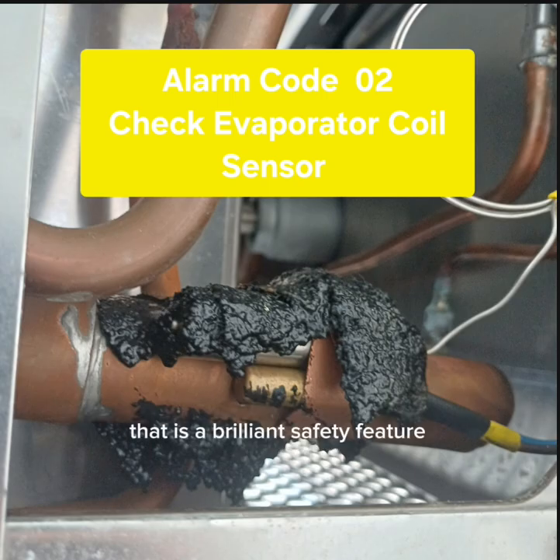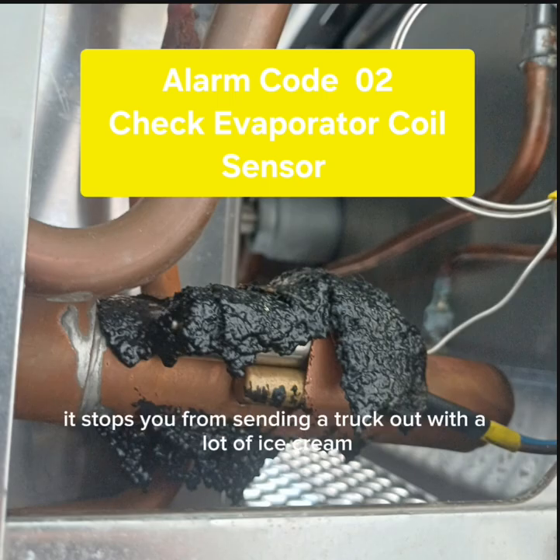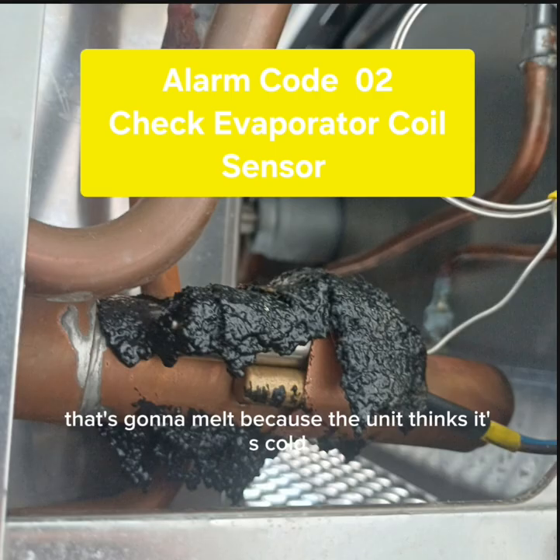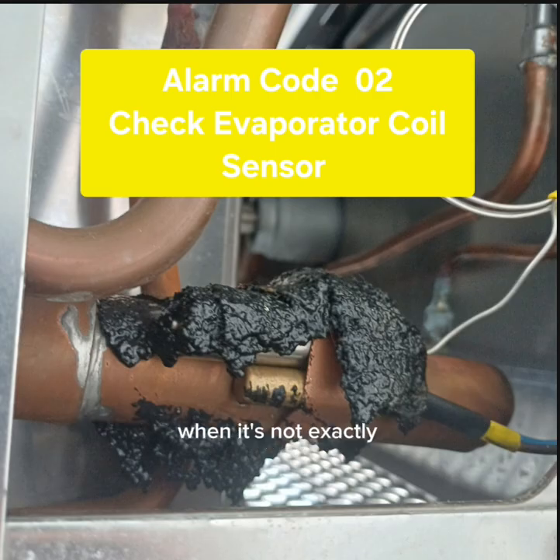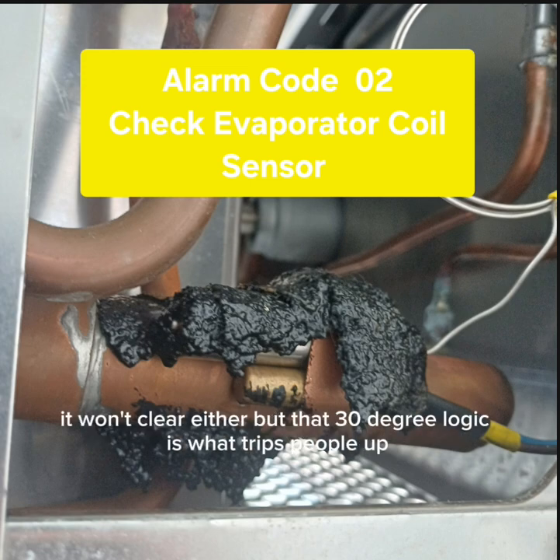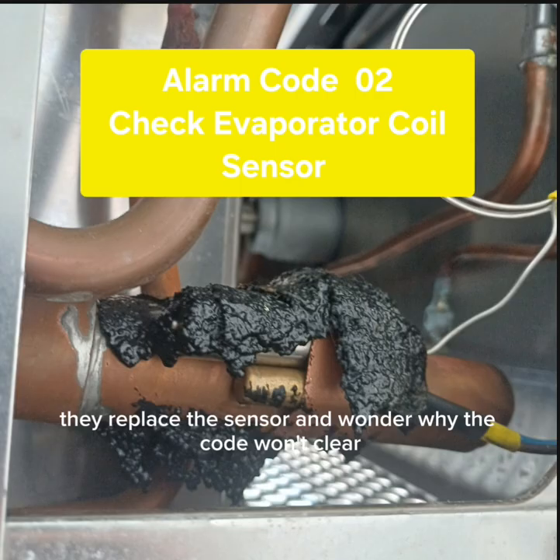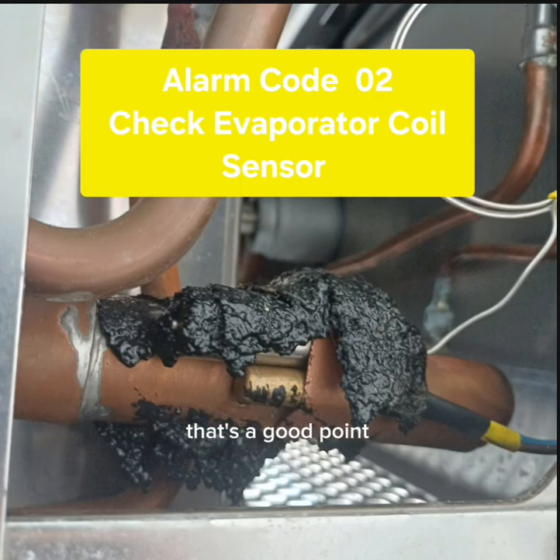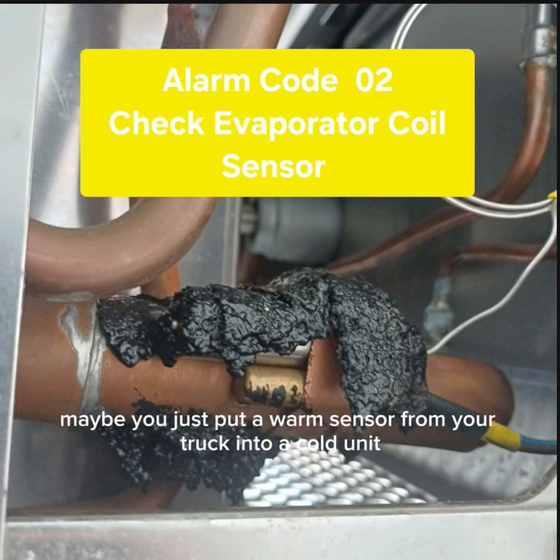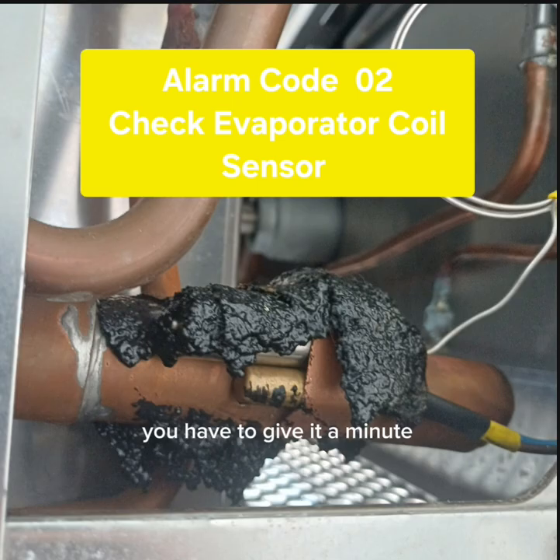That is a brilliant safety feature. It stops you from sending a truck out with a load of ice cream that's going to melt because the unit thinks it's cold when it's not. Exactly. It forces you to actually fix the problem. And of course, if it's still reading dashes, it won't clear either. But that 30-degree logic is what trips people up. They replace the sensor and wonder why the code won't clear. That's a good point. Maybe you just put a warm sensor from your truck into a cold unit. You have to give it a minute, let the temperature settle. Don't panic if it doesn't clear instantly.